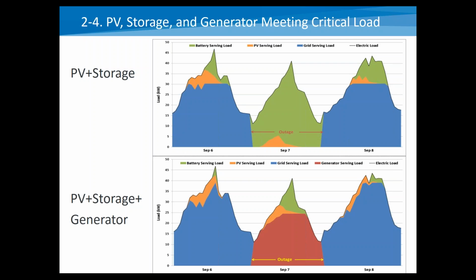On the bottom graph here, we bring in a generator. Again, on the first and the third day, September 6th and 8th, the smaller PV and battery system are being used to shave peak. There's a little bit lower savings there because you have a smaller PV and battery system in this case. But on that middle day, you can see that the generator is serving the majority of the load, but what the PV and battery system are doing there is cutting off the peak in that load, such that you can have a smaller generator and you can still meet the total requirements of the site.